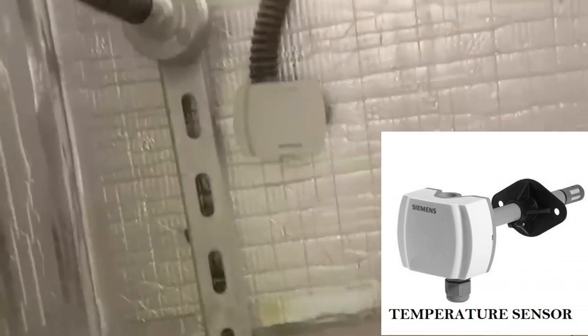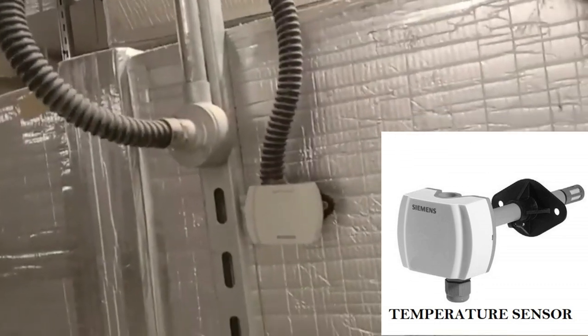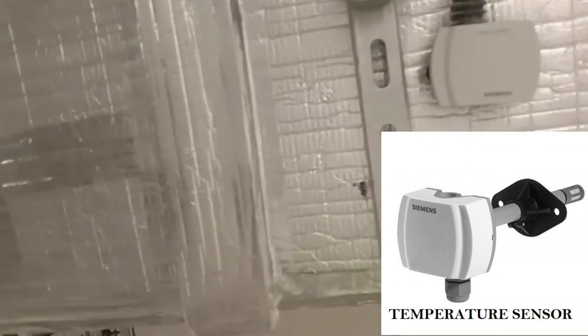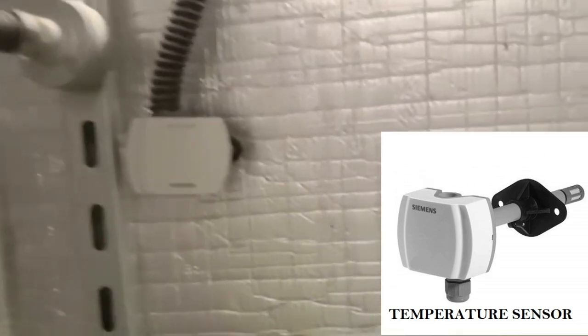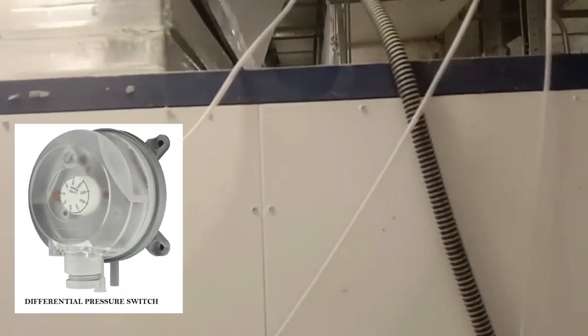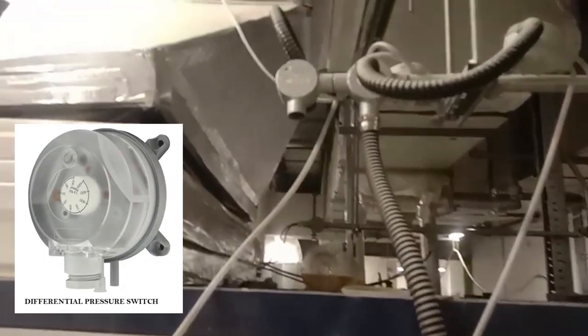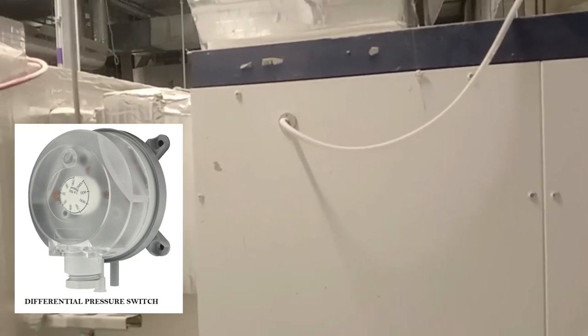So we have a temperature sensor that has been installed here on the supply or on the fresh air duct. It measures the temperature that goes inside the duct. And then from the side where we have the fresh air getting inside the duct, we have differential pressure switches, which are also installed from the beginning of where the air is getting inside, and from where we have the damper opening and sending the air inside the AHU, to measure the pressure difference between the air coming in and the air which is leaving from the damper.